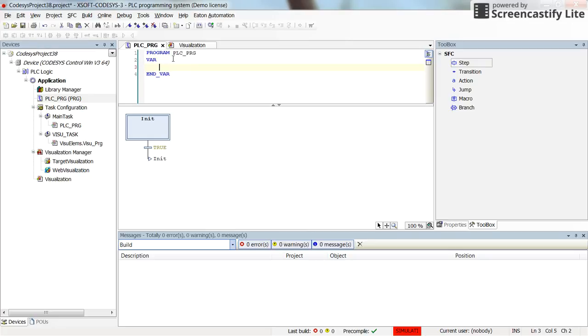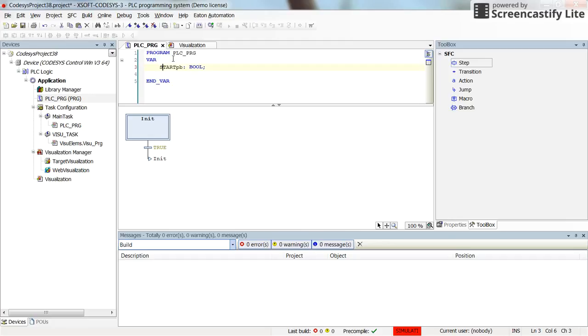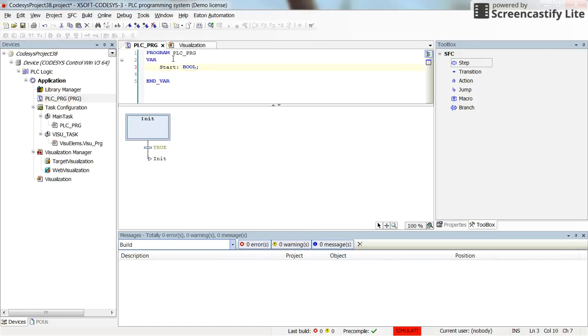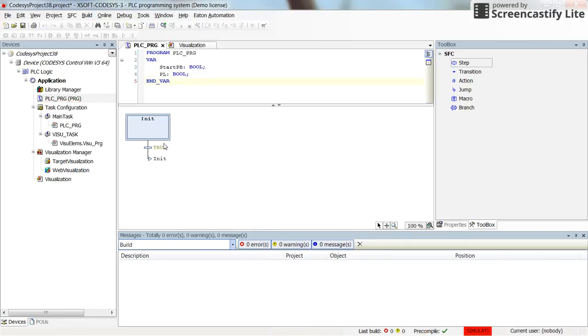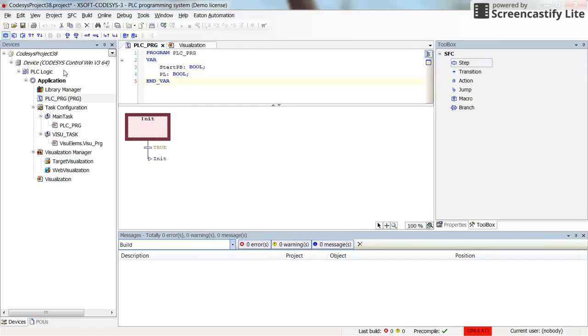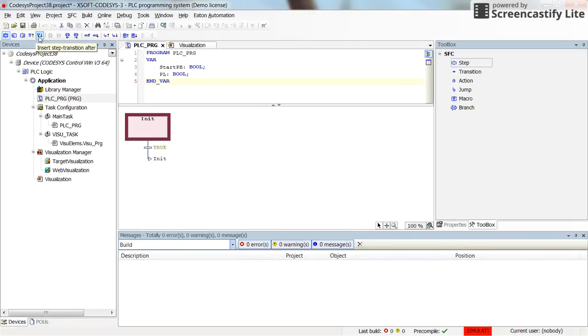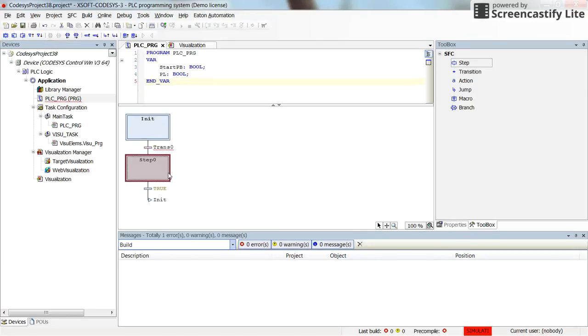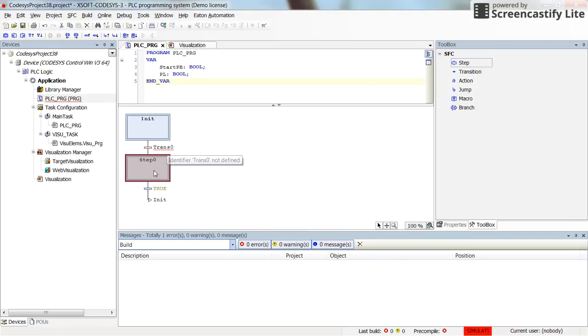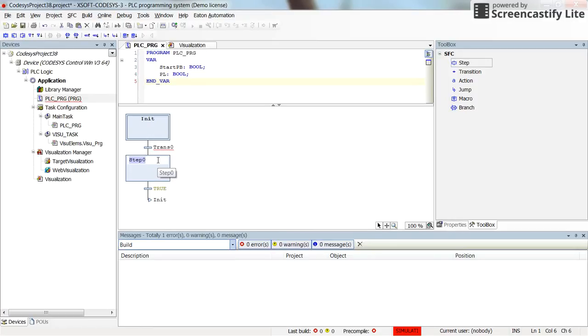I am going to declare a variable start_pb as the boolean. And now it's the point in which we are going to start the process. So here after the init, I click on the init state and then you can look here in the toolbar that I can insert a step transition or I can insert the step transition after. So if I select this one, you can see here that there is a transition which is called trans0 right now. I am going to modify it and there is a step which is called step0 by default. So I am going to change the name for this step to on_state.